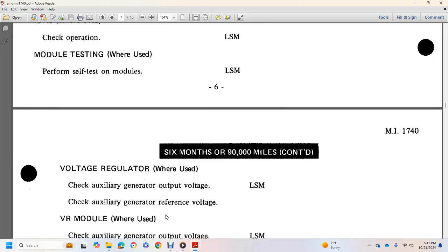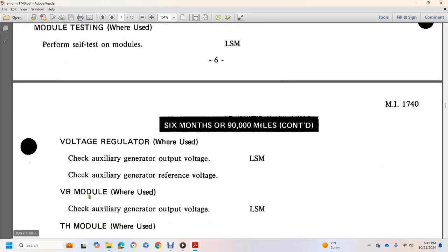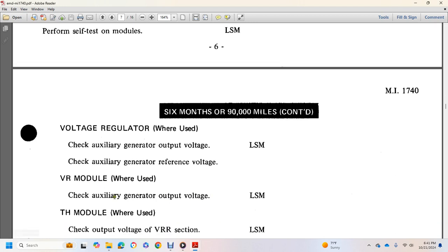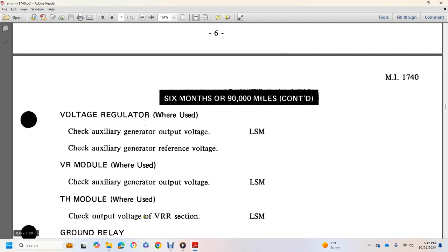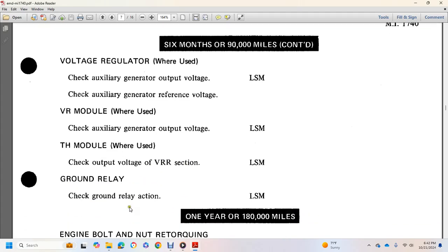Auxiliary generator reference voltage, VR module where used: check auxiliary generator output voltage, locomotive service manual. TH module where used: check output for the VRR section, locomotive service manual. Ground relay: check ground relay action, locomotive service manual.